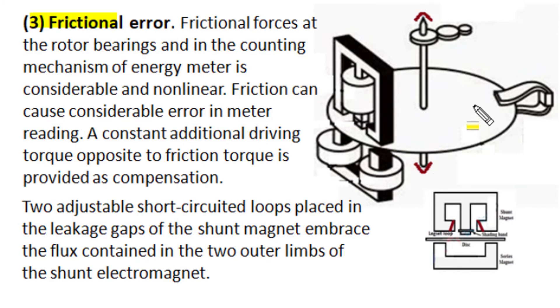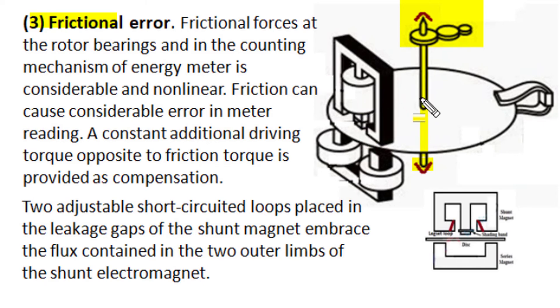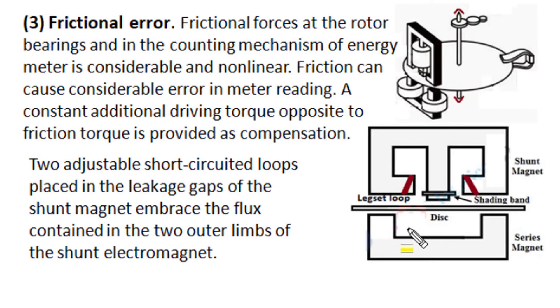Frictional forces at the jewel-pivot suspension of the spindle and in the counting and registering mechanism are not only considerable in magnitude, they are also non-linear. The magnitude of frictional forces becomes considerably higher for light load measurement when the driving torque is relatively small and the disk is rotating at a slower speed. Such non-linear and higher frictional forces can cause considerable error in energy meter measurement, especially at light load conditions. A constant additional driving torque opposite to frictional forces is provided to compensate for frictional error.